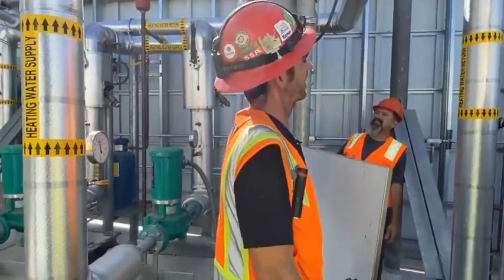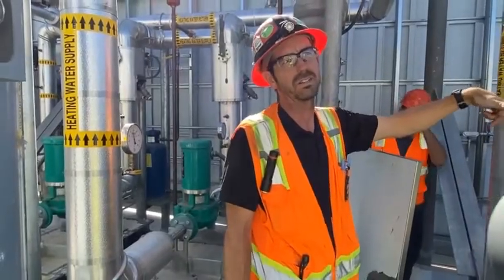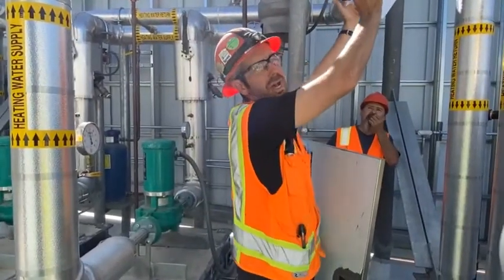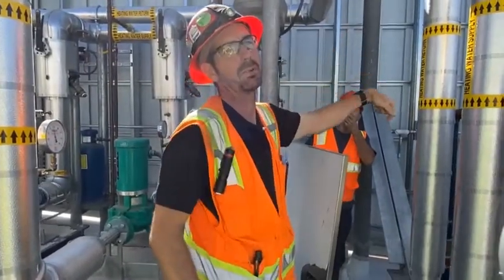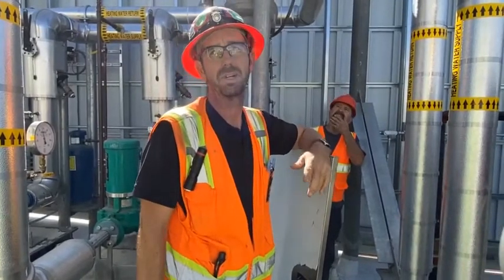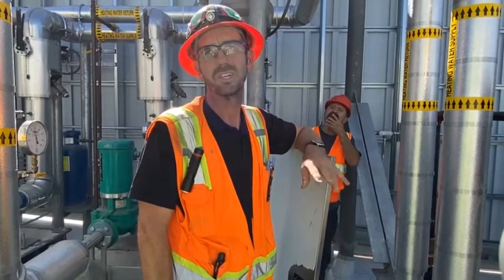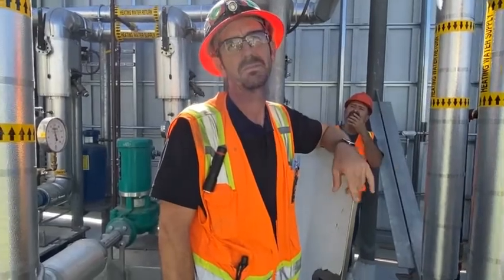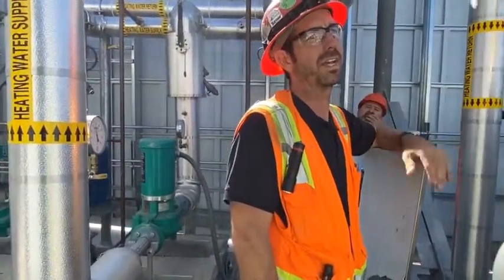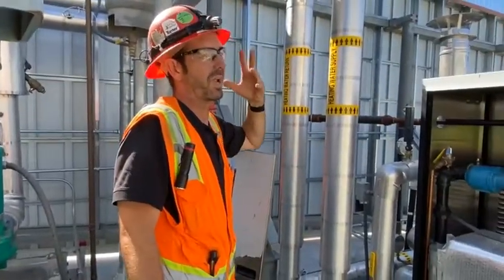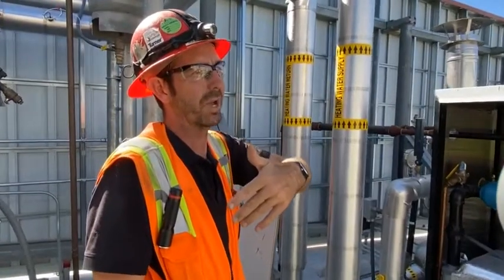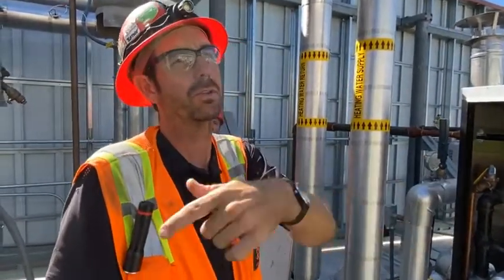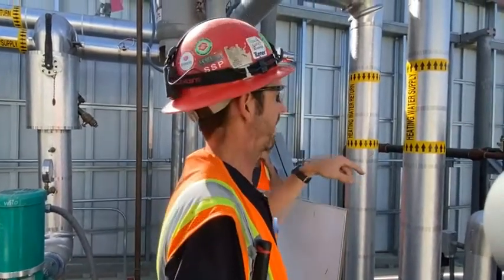The building pumps can't push water through the water heaters. The distance between the two pipes doesn't create a big enough pressure drop to be able to push the water through there, okay? Does everybody get that concept? Do you guys have primary, secondaries anywhere else? No. Okay, this is primary, secondary up here. Just for your brain, building A and B are variable primaries. All the water is going through at least one boiler at all times. Okay, primary, secondary here.